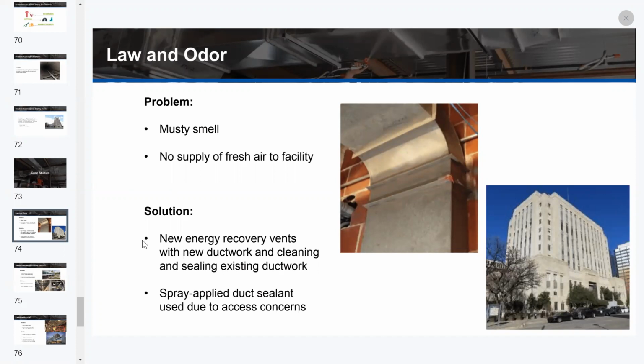Law and Odor was a historic Oklahoma courthouse. They had a sickening, musty smell, years of recirculating stagnant air, due to a failed pneumatic control system, no fresh air. The solution was to install 7 new energy recovery units to bring in fresh air, which required 1,500 feet of new ductwork installed. Additionally, they cleaned and sealed all of the existing ductwork in the building. They used a spray-applied duct sealant from the exterior of the duct due to the challenging access to the ductwork.